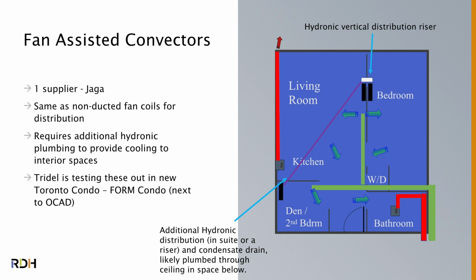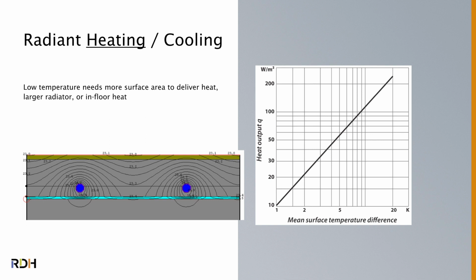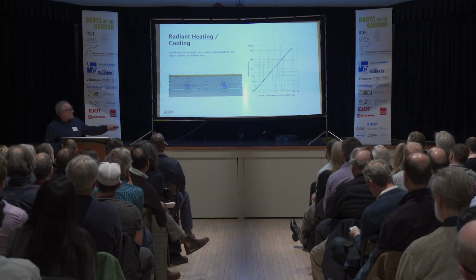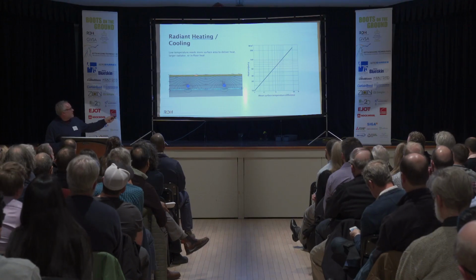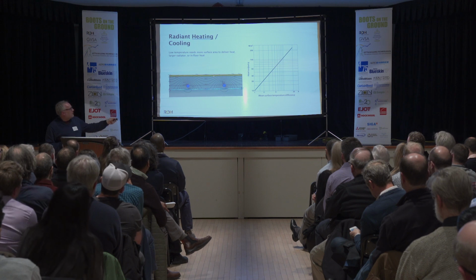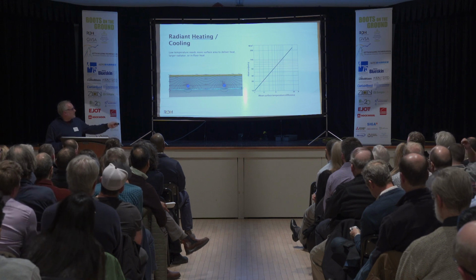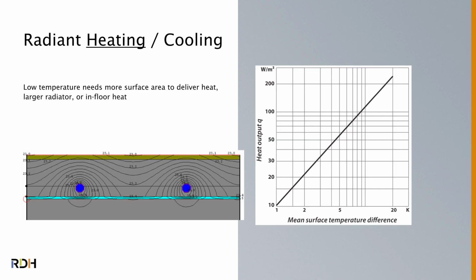Radiant heating and cooling, actually this is happening in a project in Guelph that's targeting net zero and net carbon zero performance. They're doing radiant cooling. This example here is radiant heating. This is how much heat you get out of a floor for whatever temperature the surface is. So just a little thermal analysis for a 23-degree floor. If you want 21 degrees, you're here. You're already at 20 watts a square meter.